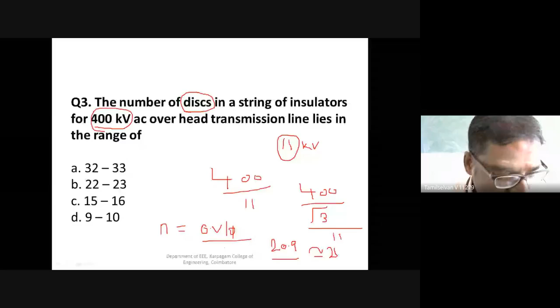Keeping safety in mind, because sometimes we cannot transmit the exact same voltage per line, there will be a plus or minus voltage. So for safety purposes, one additional insulated disc is added. The number of discs N will equal the calculated value plus 1 for safety. So N equals 21 plus 1, which equals 22.